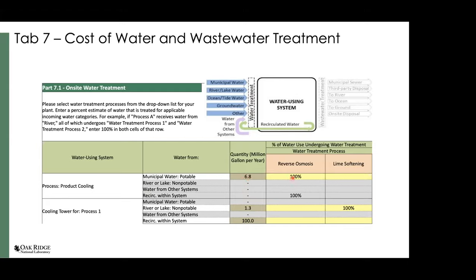And in this tab, what we are pretty much saying is how much of that water is being treated using which specific system, right? So the product cooling in this case is treated using reverse osmosis, and the cooling tower water is lime softened before entering the cooling tower. You just say what the treatments associated with these systems are. Based on this information, the tool at the back end is going to put a true cost component for each of the specific systems that you have defined.